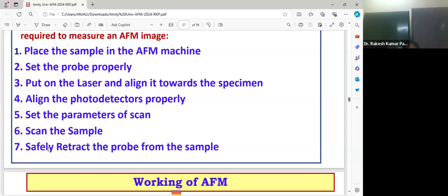If you go for very fast scanning, which most of the times happens because we remain in a hurry and just put the sample and set it for fast scanning, that is not good. It will damage the tip. Tips are very sensitive. We must take care of it. So we need to go for a slow scanning rate. Whenever you use a slow scanning rate, resolution will be far better, and you will get the best picture quality. You can easily identify each and every atom. You can even count them. You can detect the defects.